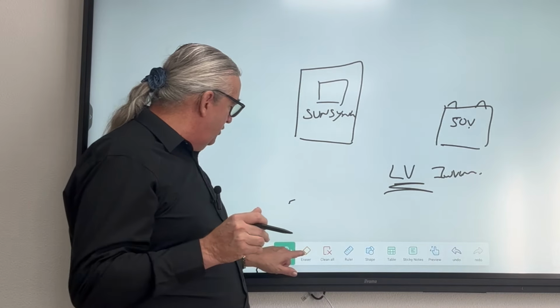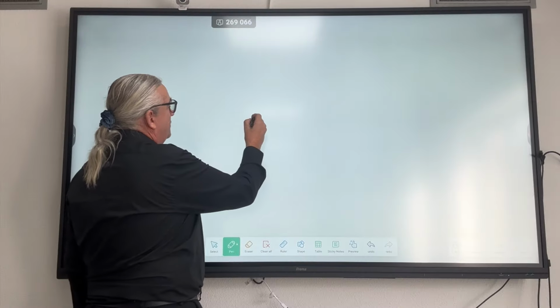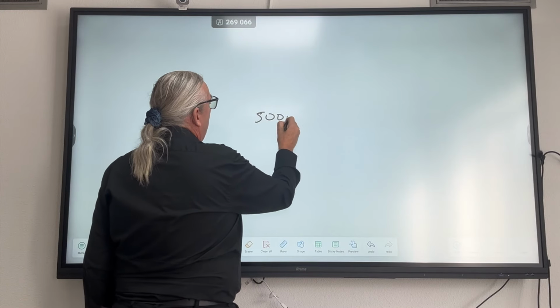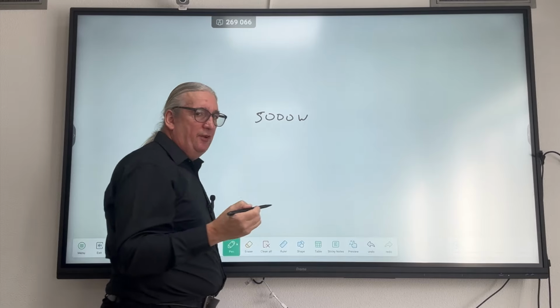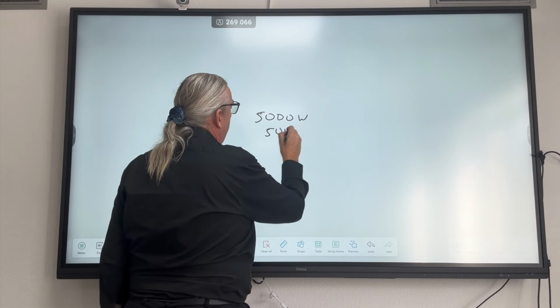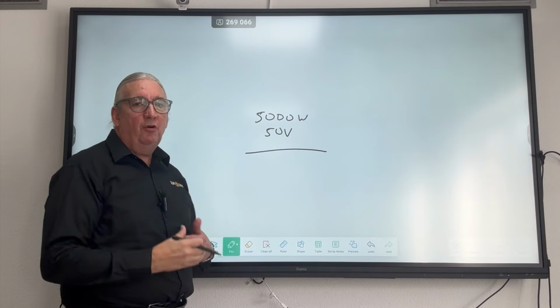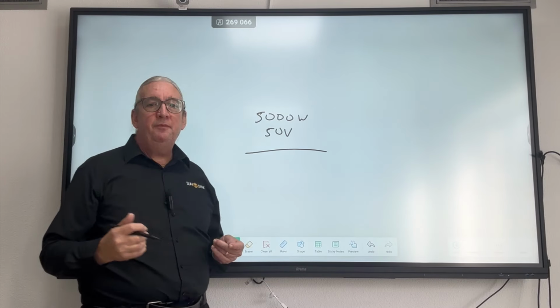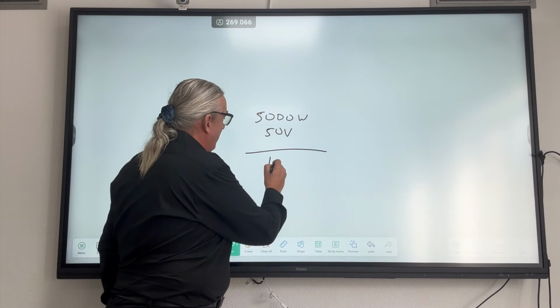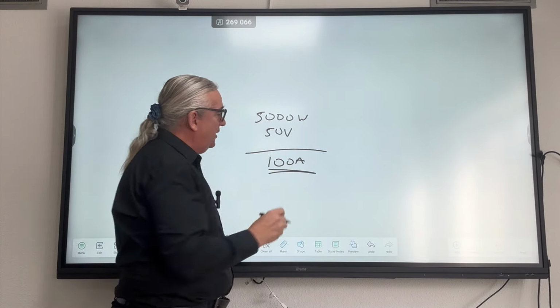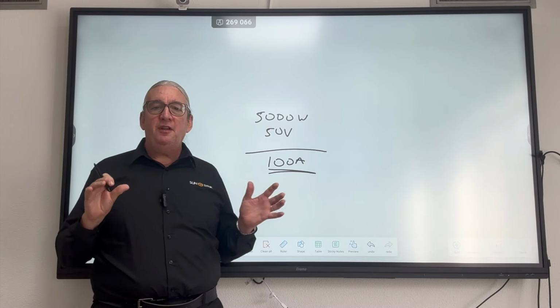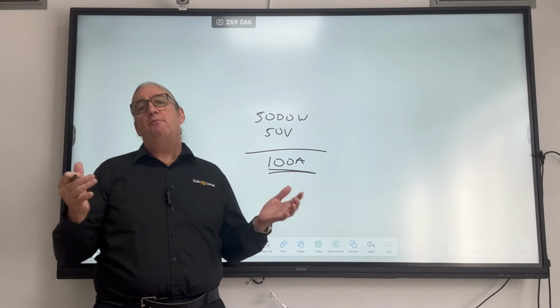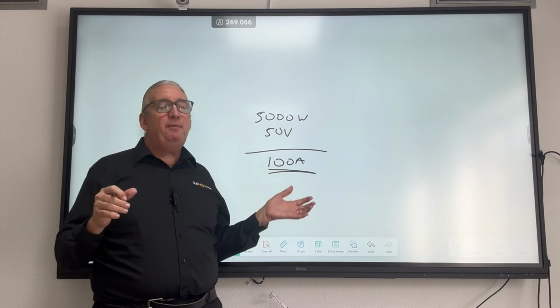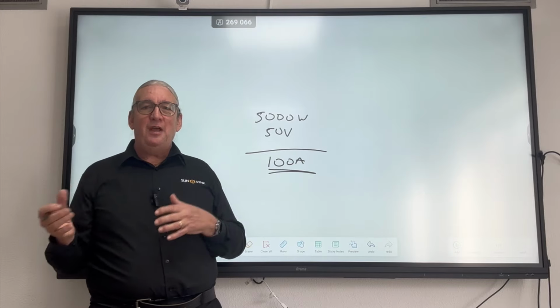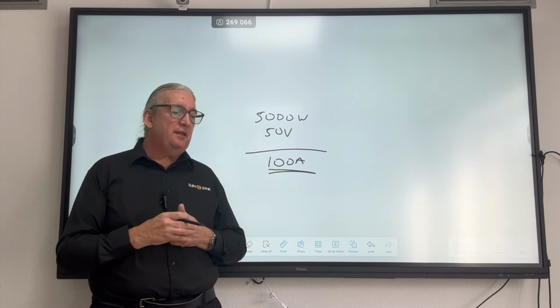So why would you ever use a low voltage or high voltage inverter? Suppose I've got a 5,000 watt, or 5 kilowatt, inverter with a 50 volt battery - what current can it draw? Simple: 100 amps. That means my battery connection has to carry 100 amps internally within the inverter. It's got to be rated for more than that, but the general running power is 100 amps, so everything - the cable, everything - has to be protected to that level.